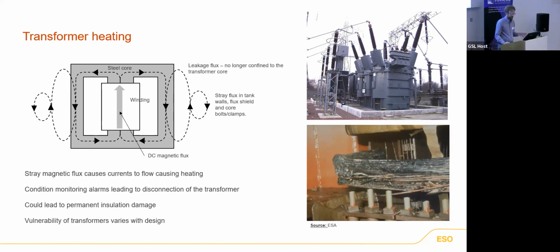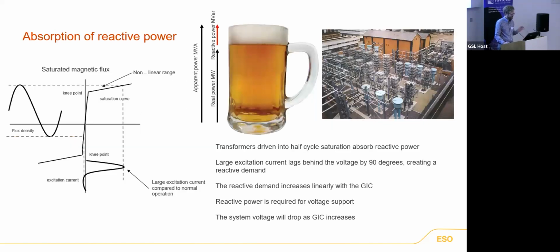Okay, so we talked about the flux and the heating effects. That's where our heating can come from and possible damage. Now we're talking about the absorption of reactive power, which is another secondary effect from your GIC. So first of all, what is reactive power? Well, a simple way to think about it is that reactive power is required on an AC power system to set up electric fields and magnetic fields so that the real power that actually does the work can be transmitted across the network, from the generator to the demand. Without those magnetic and electric fields, it just doesn't happen. So you need some reactive power.